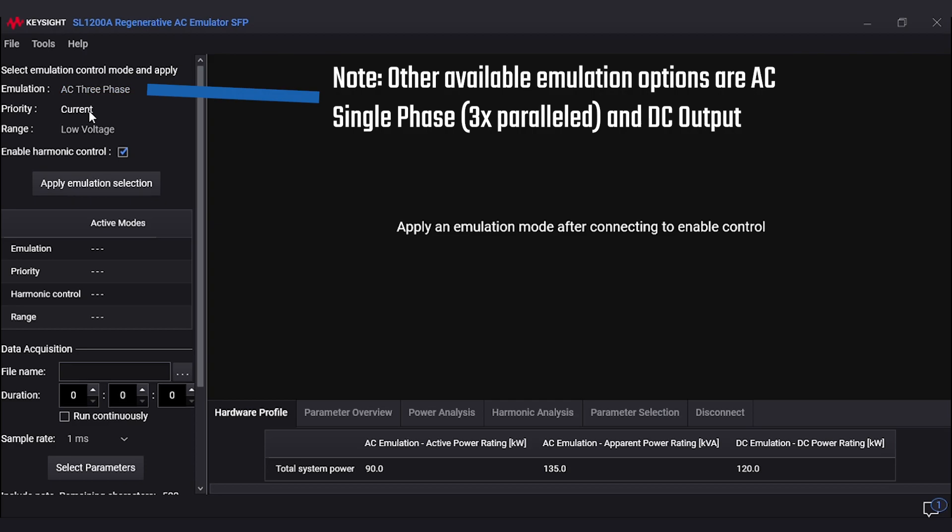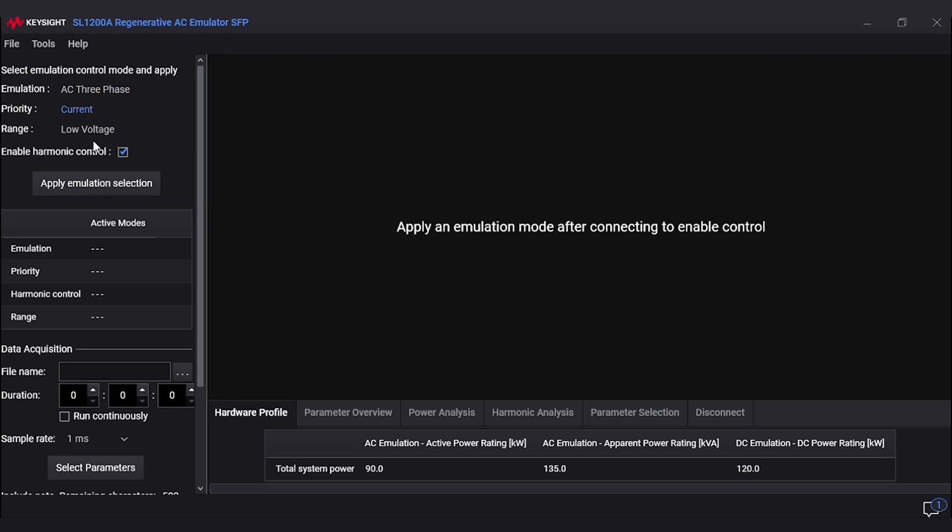The priority choices are current and voltage. We will be using voltage for today's test. The options for range are high and low range. We also have a harmonic control function we can check on or off depending on the test. I'm now going to hit apply emulation settings.